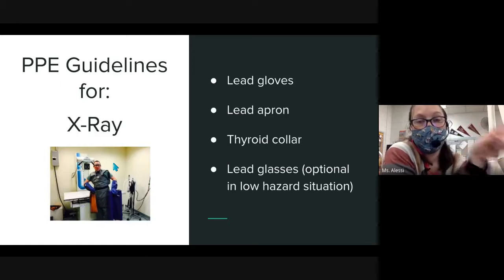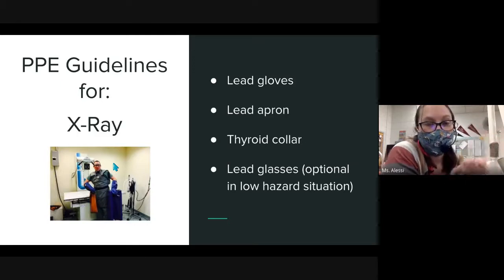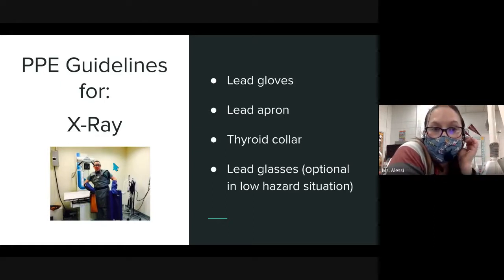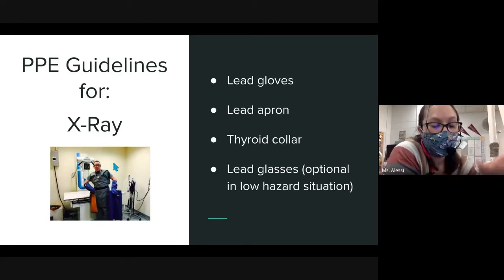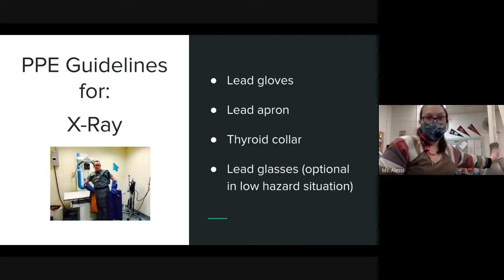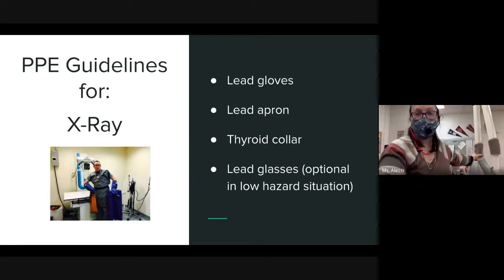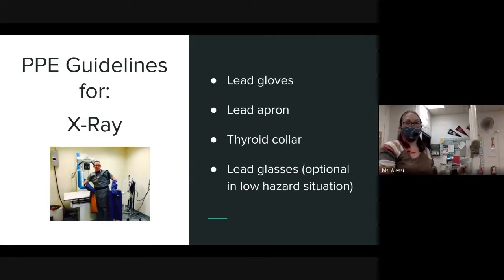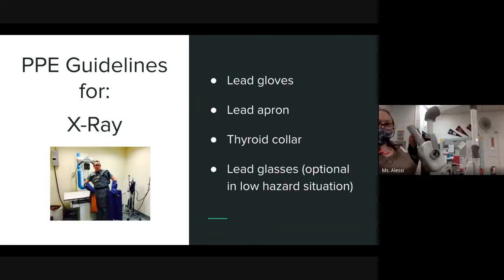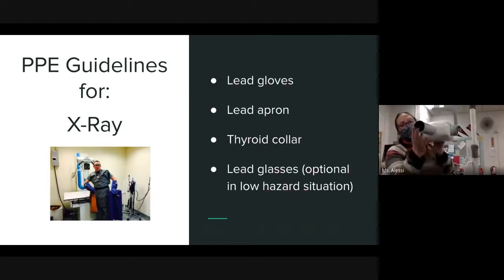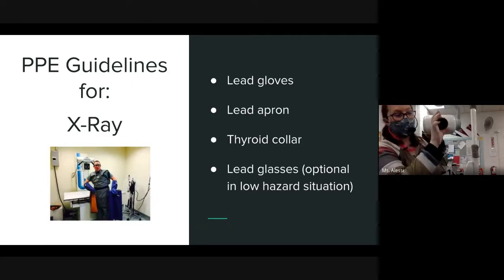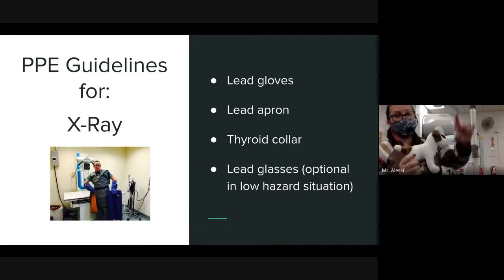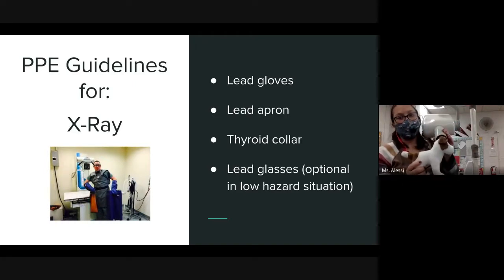You'll have a light beam, but your radiation will go outside of that beam. Okay, so that is why all of that lead is important, and that lead will protect the beam from going through. So especially depending on the type of machine you're using, we've got this big thing right here. It is actually an old dental radiograph. So the radiation comes out of that little hole. The animal, if it's right here, there's a whole bunch of space though that radiation is going to be able to spread from. So we want to make sure that we are protected when we're in there.